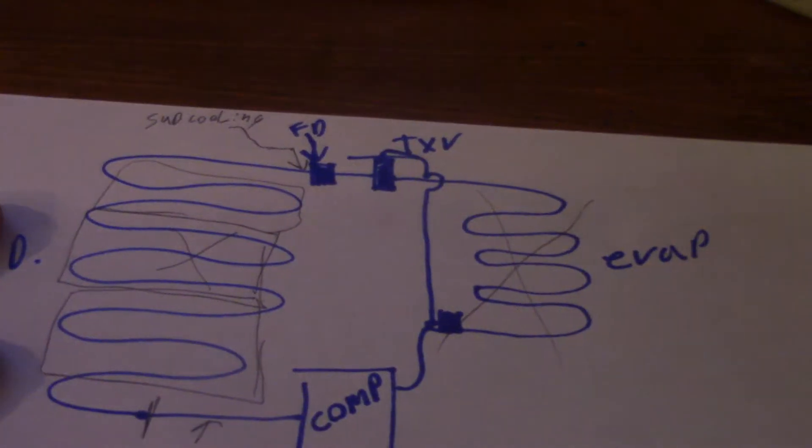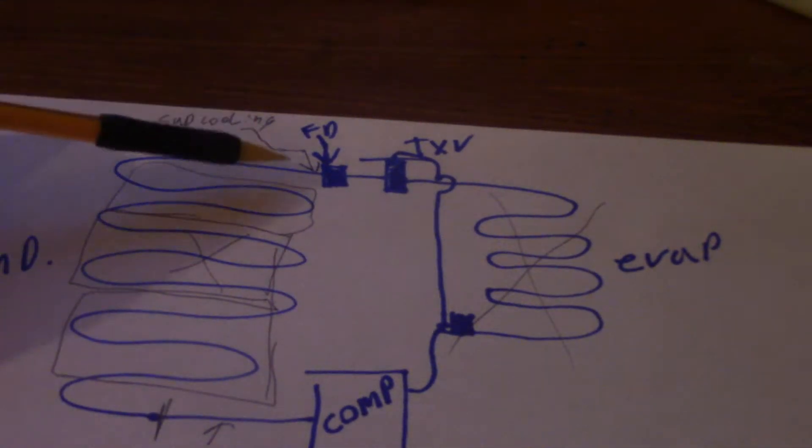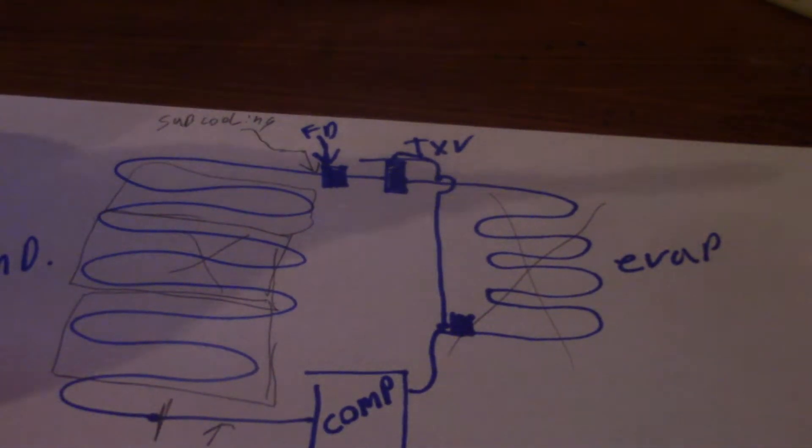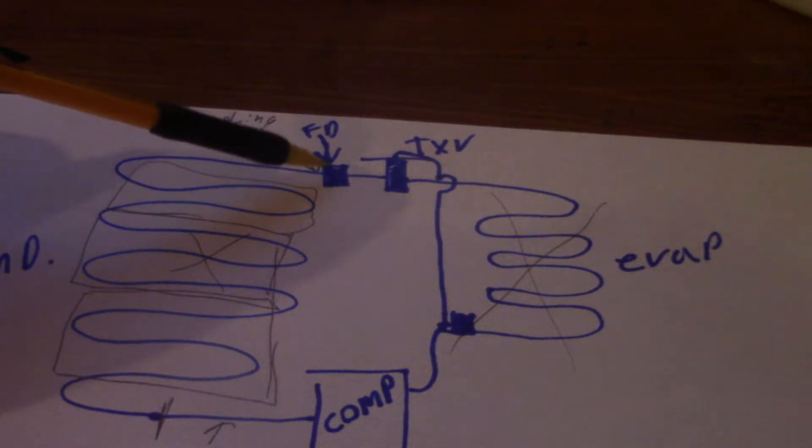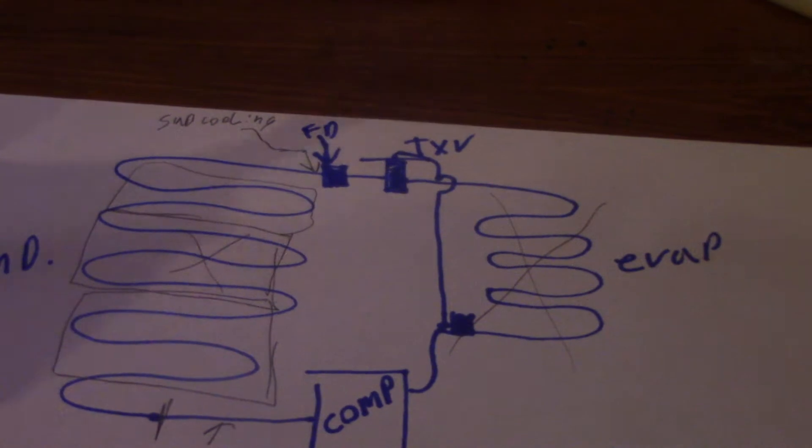I've got to move my fat hand out of the way, right? Subcooling is taken right here. That's where you get a pressure and temperature. Not necessarily saying before the filter dryer, I'm just showing the filter dryers in the liquid line with the TXV.